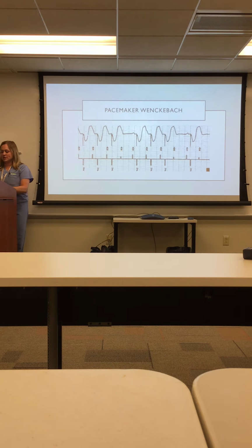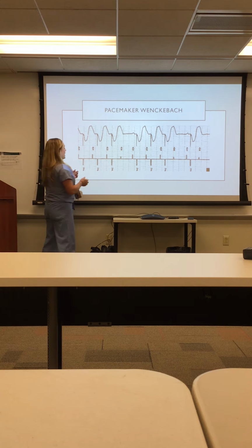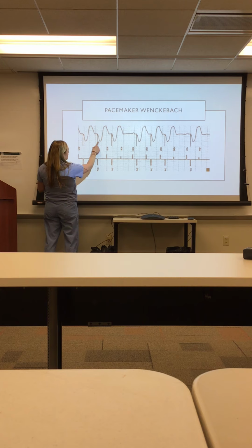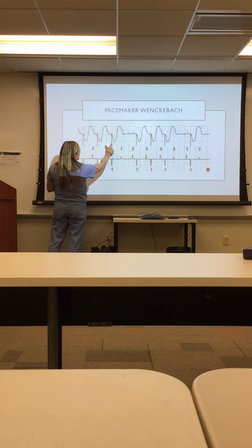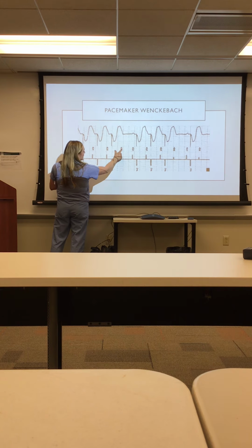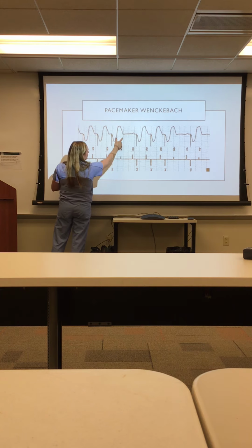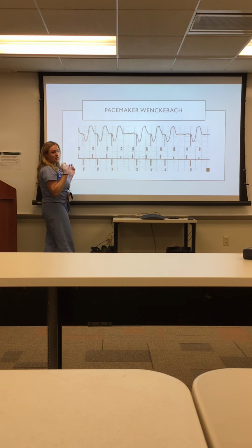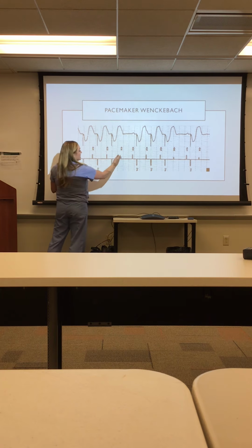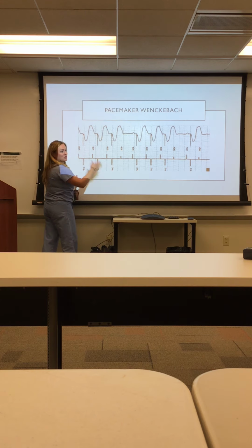So here's kind of an example of pacemaker Wenckebach. When it goes just above that 130 we were talking about, you're gonna start to see that the device, and I don't know if you usually see this with temporaries, but you could. So the pacemaker is marching along here. It's starting to get up into the 130s like we said. So we've got paced, paced, paced, and then you almost see a block here. Well, this atrium is going too fast, and this is gonna fall into what we call a blanking period, or PVARP. So the device is meant to blank that out so that it stops tracking at those higher rates.